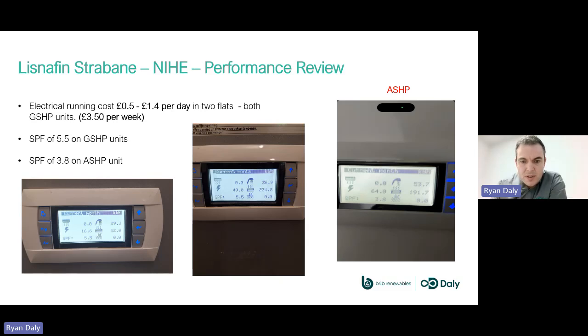So just looking at performance so far for Lisnafin, the running cost for the ground source heat pump. Interestingly, the lowest there is 50p a day over the winter. And you can see on the bottom left photograph, that was taken on the 9th of February, and that's how I worked that out. It was 16.6 kilowatts used in electricity. There was 62 kilowatts of heat produced in total, but you can see from the figure above, half of that went to the hot water production.